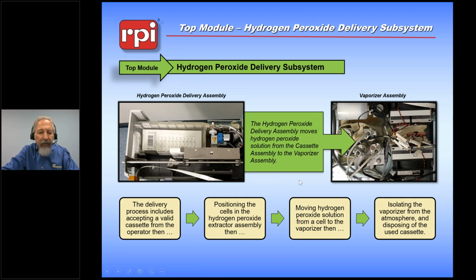We move the peroxide through the system and out into the chamber. Now, one thing I wanted to point out about this system is this valve right here. If you are looking for a vacuum leak in this system, in the NX, the very furthest spot that you can find a vacuum leak is actually this valve. It's the very furthest place from the chamber. And from this valve, you need to have a solid vacuum system. So if you were looking for a leak, you can start there, go through the transfer tubing, go through the various fittings that are involved in the vaporizer condenser assembly, and you should be able to track down some leaks at that point.